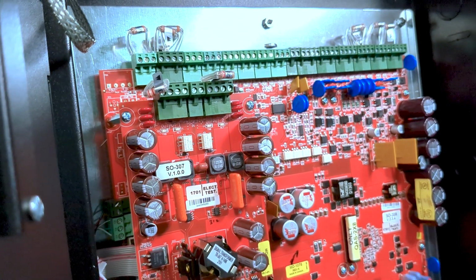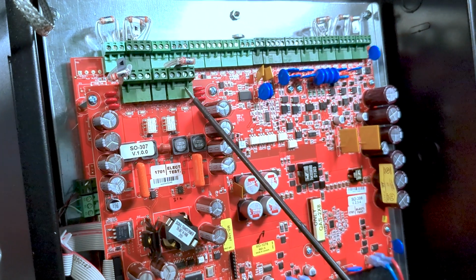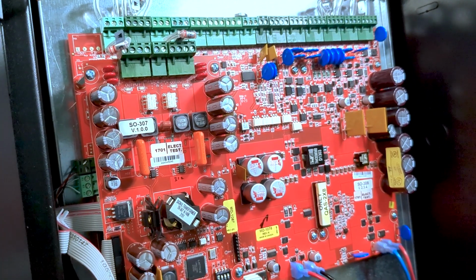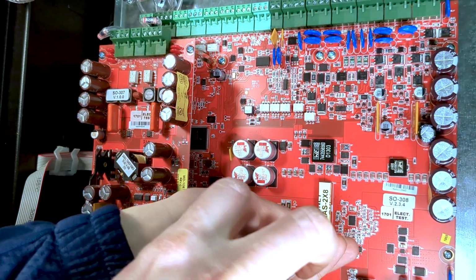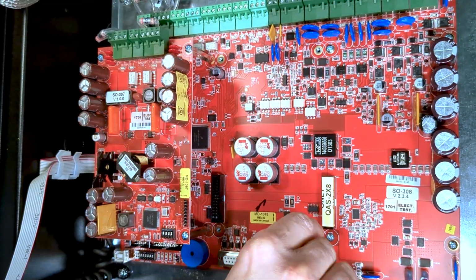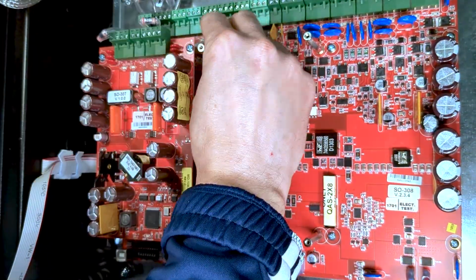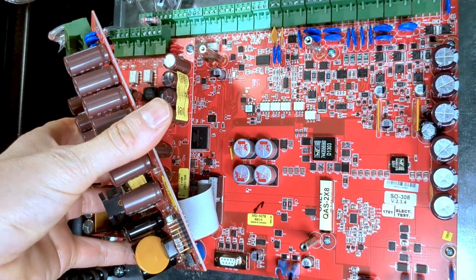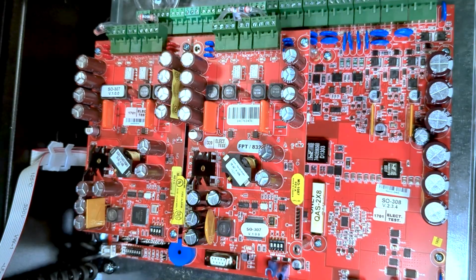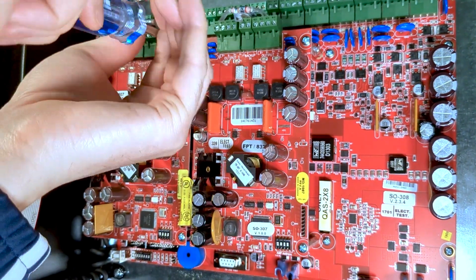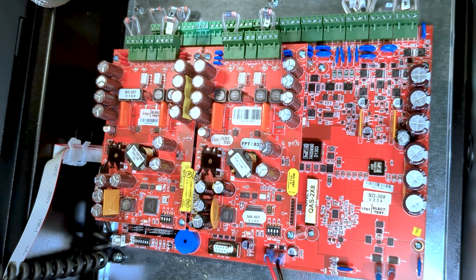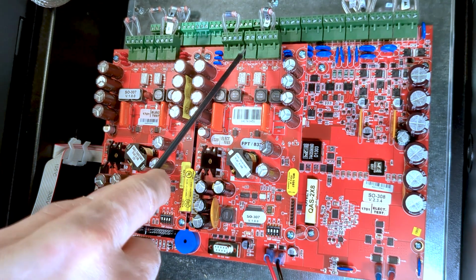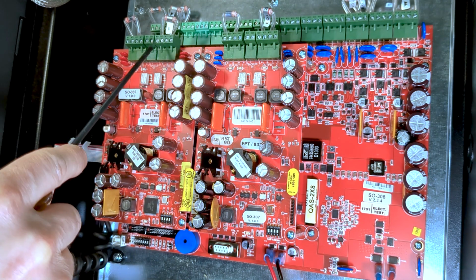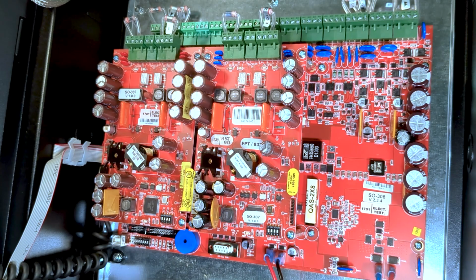Taking a closer look at the QAD30 amplifier, we have two Class A or B outputs that share a total of 30 watts combined. Next, I will demonstrate the installation of the secondary QAD30 amplifier. Now that we have the second QAD30 installed in P6, we can set our dip switch addresses on the bottom to 1 and 2. We now have provisions to use the second QAD30 as a backup amplifier by connecting the backup input to either A or B output from the first QAD30 amplifier.